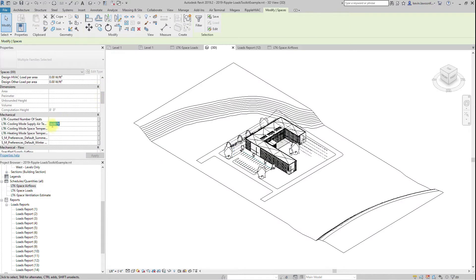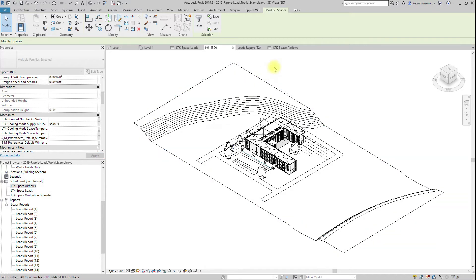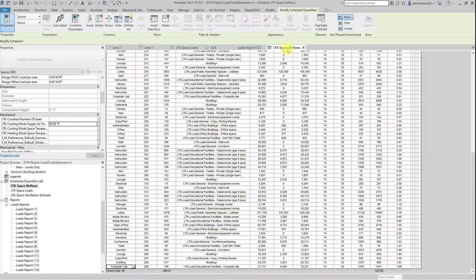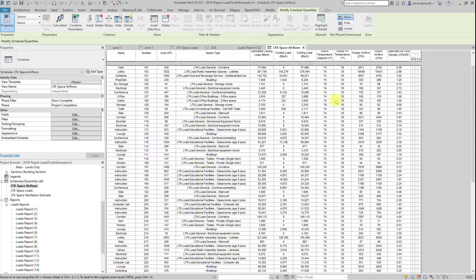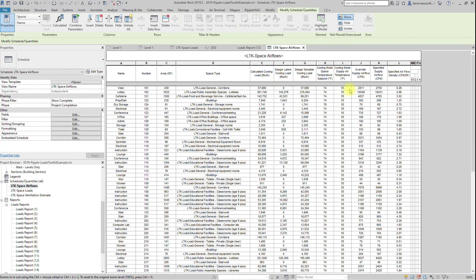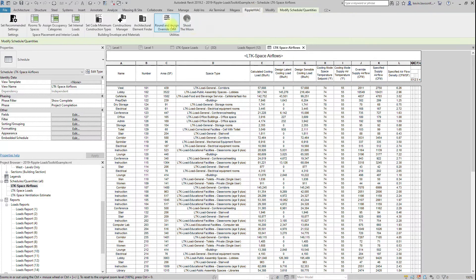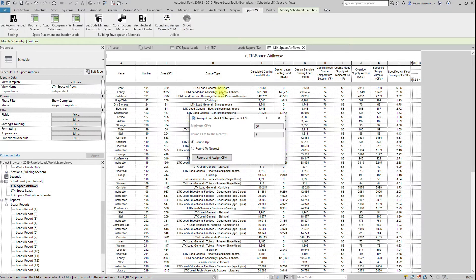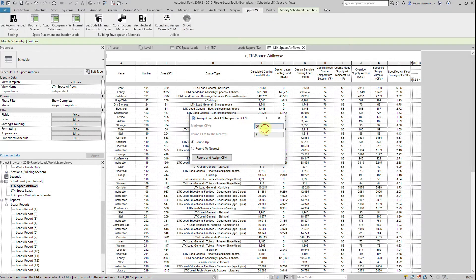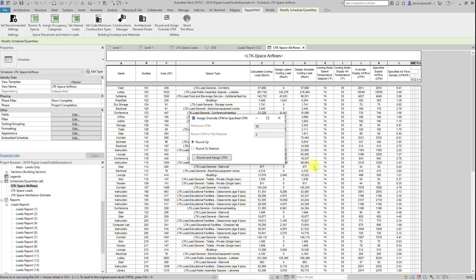You can select all spaces in the schedule, then click your default 3D view, and then change the parameter for all spaces selected in the properties window. You can then round and copy this number to the specified supply airflow parameter by clicking the Round and Assign Override CFM button. It will also set a minimum CFM so that you don't end up with something below what can be balanced.